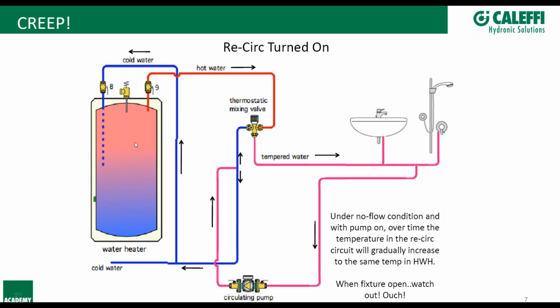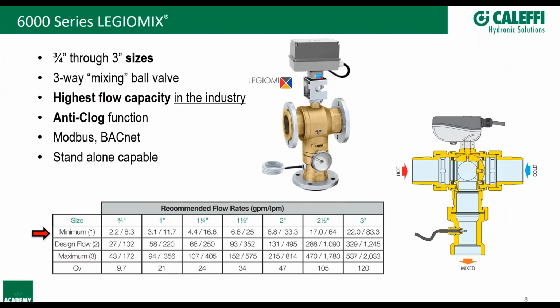And we have a solution for that as well. That's actually going to be our LegioMix. Okay, so not only can our LegioMix, it's a great mixing valve first and foremost. It's ASSE 1017, so it's going to comply with all the standards. It's low lead and everything else, but it has the ability to do that thermal disinfection cycle if you have an application for it. You don't have to use it if you don't want to, and by default, all the thermal disinfection functions are off. But it also has the ability to eliminate recirc creep as well and maintain that temperature at a very safe temperature.